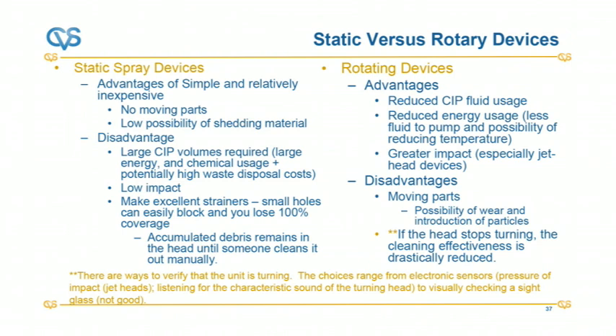Rotating devices, advantages: reduced CIP fluid usage, reduced energy usage, greater impact, especially with the jet head devices. Disadvantages: moving parts, possible wear and introduction of particles. If the head stops turning, the cleaning efficiency or effectiveness is drastically reduced. I want to say there are ways to verify the unit is turning. That might be electronic sensors that will listen to the sound of the rotary spray head and detect it if it changes. There will be a certain sound that you can analyse and check even with a relatively simple computer system.